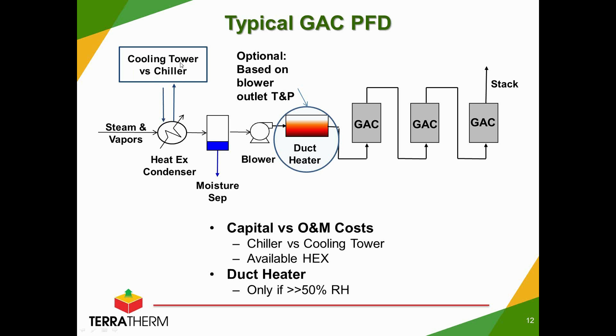I'll talk a little bit here about choosing the right cooling approach, whether it's a cooling tower versus a chiller. I've got some slides that will follow on that. The point of highlighting the duct heater here is that you don't always need them. Based on the heat of compression through the blower, we would expect to see a temperature rise. And based on the temperature-pressure curves that I showed you earlier, if we can avoid the extra energy added through this duct heater and get at or below, or pretty close to, the 50% relative humidity that we talked about, then as often as we can get away with not running a duct heater, we would elect to do that.